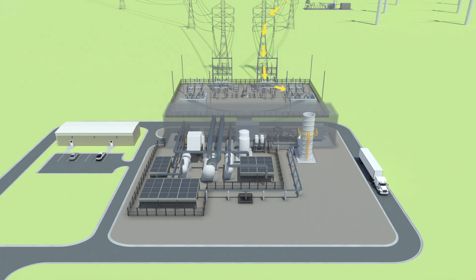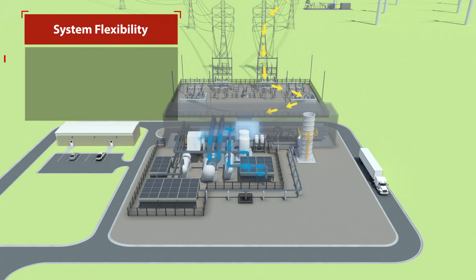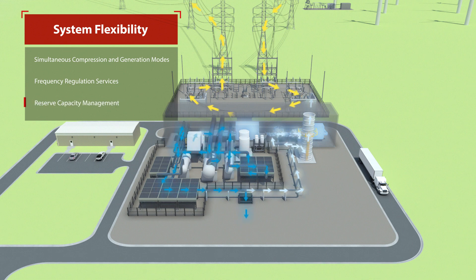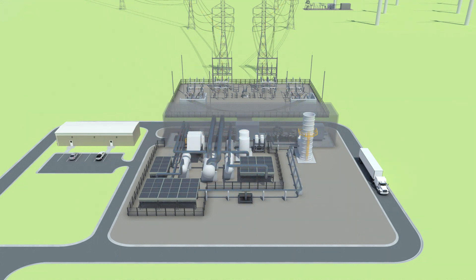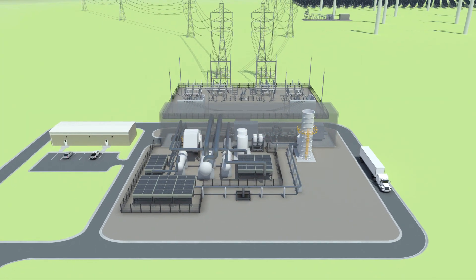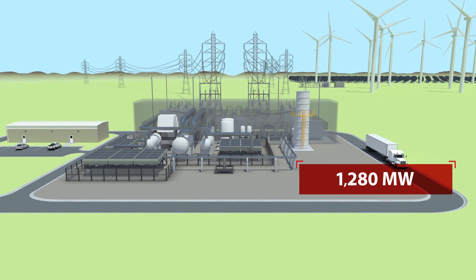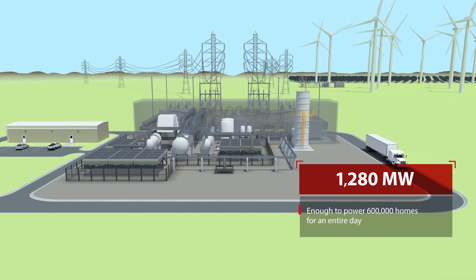During intermediate hours when consumer demand is moderate, the Dresser Rand SmartCASE can produce electricity while simultaneously diverting some compressed air aside for storage. At full capacity, the Dresser Rand SmartCASE plant, consisting of eight trains, is capable of generating 1,280 megawatts — enough to power 600,000 homes for an entire day.